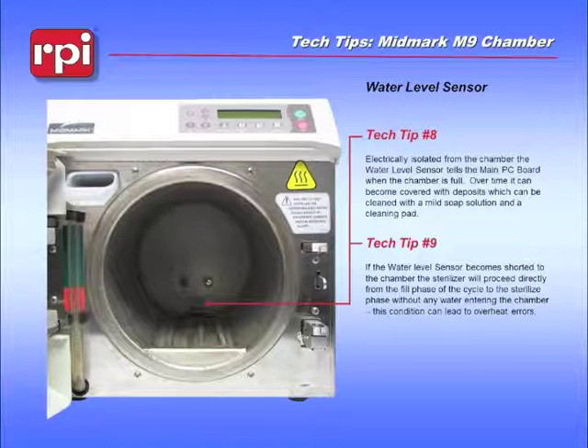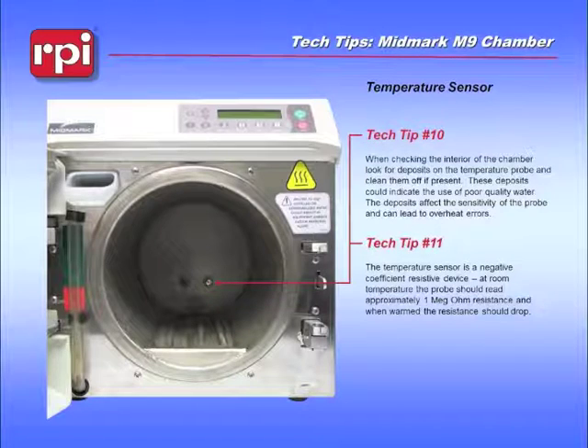So the water level sensor needs to be electrically isolated from the chamber in order for it to function properly, in order for it to complete the circuit. The ground path needs to be fully established between the circuit board and the frame of the machine, and there is a seal within that water level sensor keeping it isolated from the chamber that needs to be solid without any leaks. The temperature sensor needs to be clean.